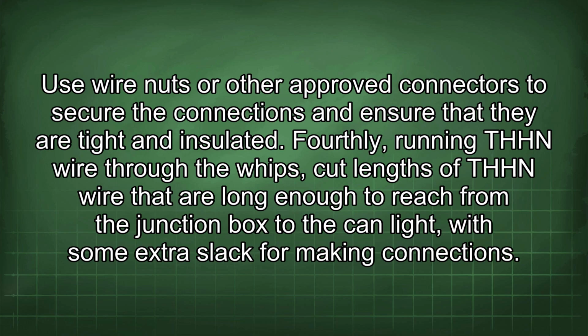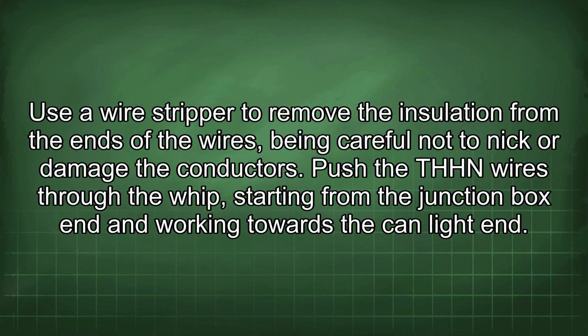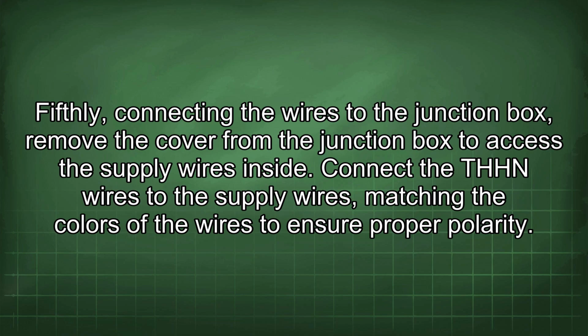Fourthly, running THHN wire through the whips. Cut lengths of THHN wire that are long enough to reach from the junction box to the can light with some extra slack for making connections. Use a wire stripper to remove the insulation from the ends of the wires, being careful not to nick or damage the conductors. Push the THHN wires through the whip, starting from the junction box end and working towards the can light end. Fifthly, connecting the wires to the junction box.